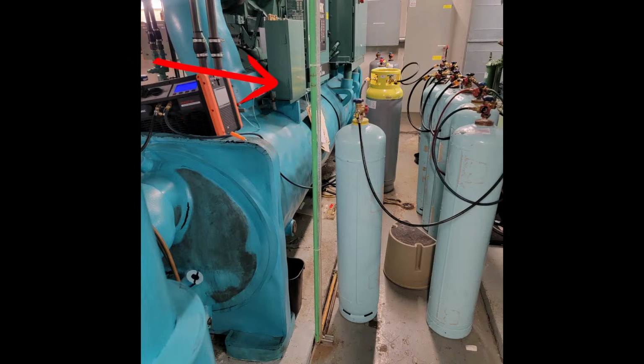To recover or charge, you just flip the hoses the other way. In a direct recovery example, the outlet of the recovery machine goes to the tank instead of the chiller. For a recovery here, instead of pulling vapor from the chiller, we'd pull vapor from the recovery cylinder, then push that vapor into the chiller to push the liquid out. That's where the whole push-pull concept comes from - we're pulling here and pushing vapor there.